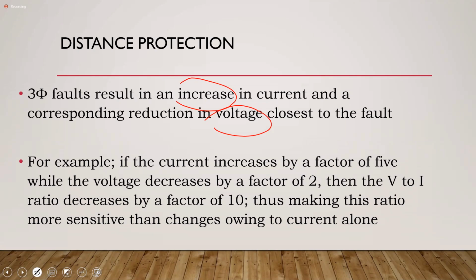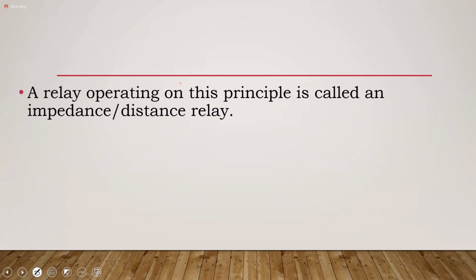So what we are saying here is, if the current increases by a factor of 5 while the voltage is reduced by a factor of 2, then the ratio would decrease by a factor of 10. All right? Which means that the impedance, which is what you're measuring, would be smaller. Okay? Don't stretch your mind over this. Just understand the basic principle. The principle is reduction in voltage, increase in current, which means reduction in impedance. And as I said, the principle here is that of an impedance relay.